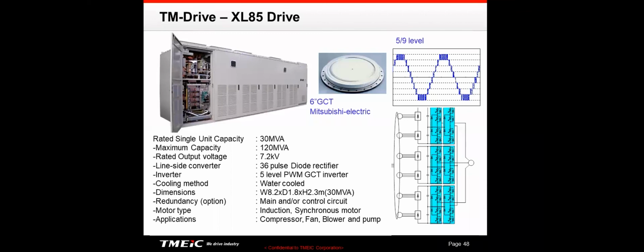That's a 30 MVA, or about a 30,000 horsepower lineup. And if you put 4 of them in parallel, you can get 120 MVA, which would be more than 120,000 horsepower. Do drives get that big? Yeah, you get into some really, really big medium voltage drives. And in this case, this is a 5 level output. You can see the output waveform there.